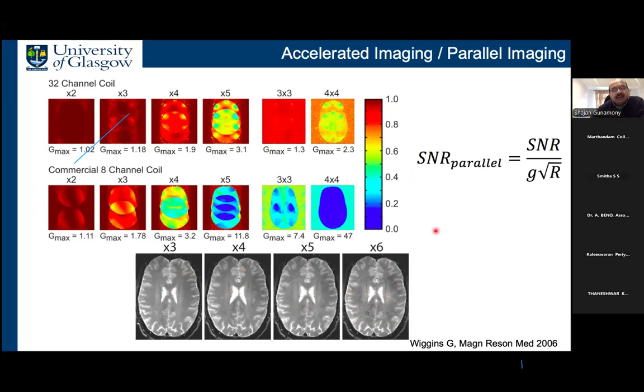So in this example here, we see the accelerated image with an acceleration factor of 3 to 6. Even at such high acceleration factors, you can see the SNR is decreasing, but you don't lose much information. So that's the benefit of having these kind of high channel count coils. Okay, so that concludes my first topic, which is a general introduction to transmit and receive coils.